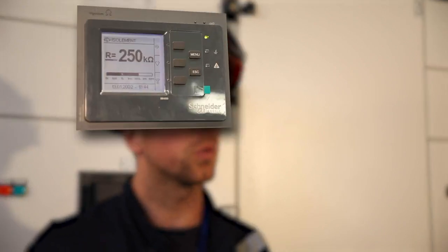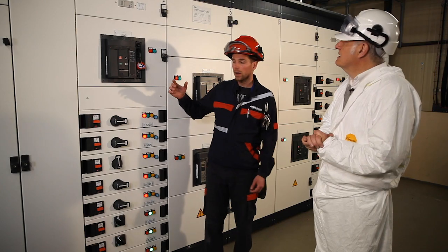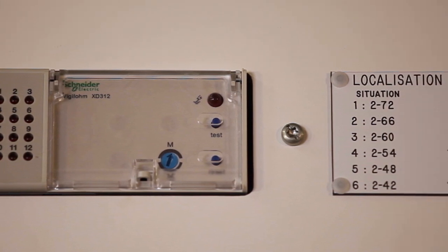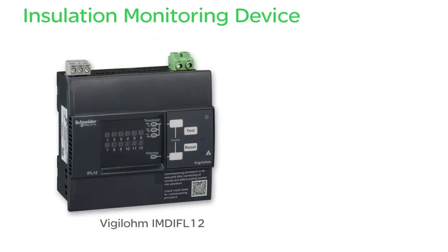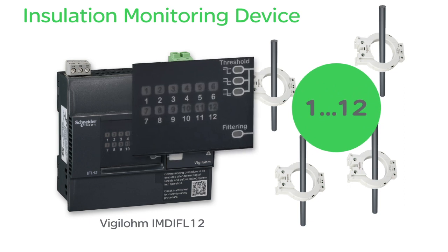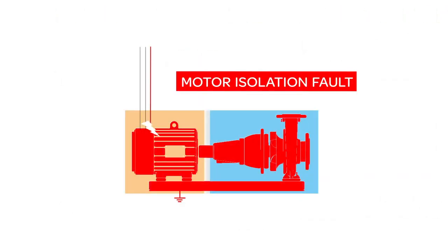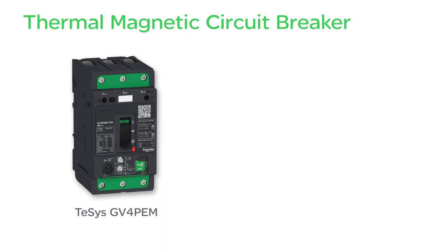We monitor our entire low-voltage distribution through a permanent insulation controller that monitors the entire low-voltage panel. Fault locators have been integrated to monitor the insulation of the motor circuit by circuit. The Vigelom IM-400 measures and displays the insulation resistance of an electrical installation. The Vigilohm IMDIFL12 has replaced the XD312; with its current cores, it can monitor 1 to 12 motor circuits, and LEDs are used to locate insulation faults. The monitoring of insulation faults can be complemented by the protection of persons who may accidentally touch the motor. The GV-4 PEM circuit breaker incorporates a device that trips in the event of an insulation failure and also protects against short circuits and overloads.